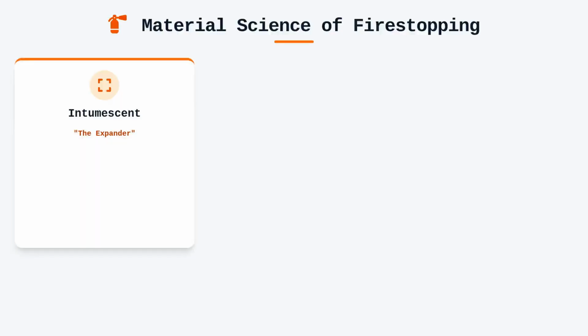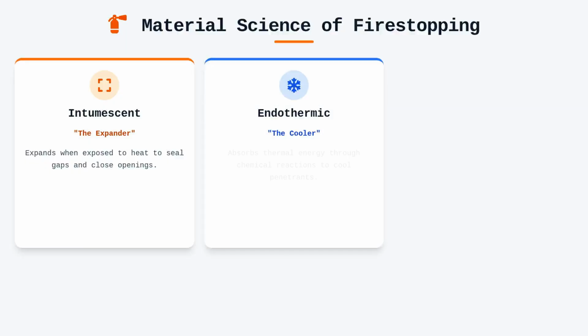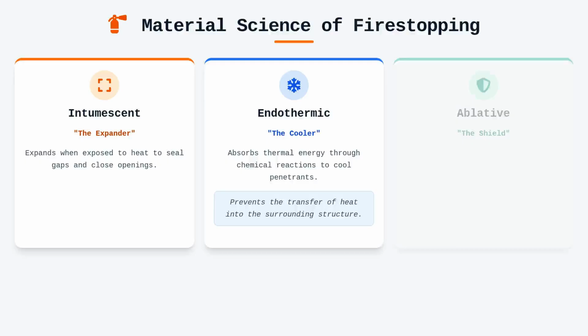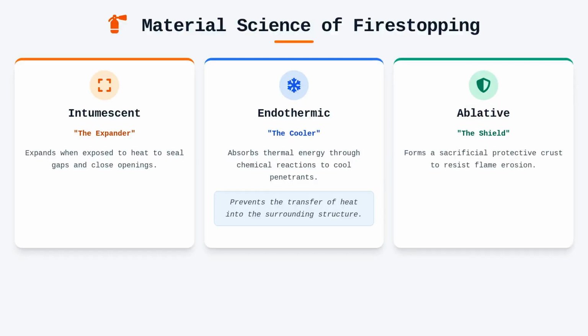Understanding the material science behind fire stopping is paramount for any designer. We classify these materials based on their physical reaction to heat, such as intumescent, endothermic, or ablative properties. Intumescent materials are particularly interesting because they expand when exposed to fire, effectively closing off openings and sealing gaps created by melting cable jackets. Endothermic materials absorb heat through chemical reactions to cool the penetrants, while ablative materials form a crust that resists flame erosion.